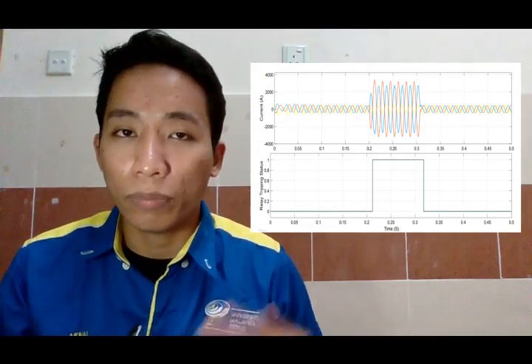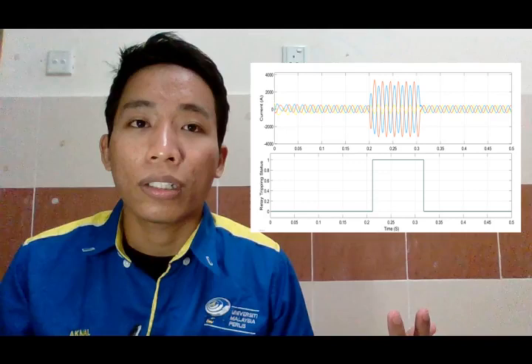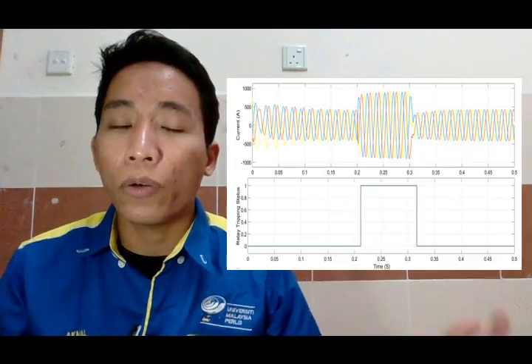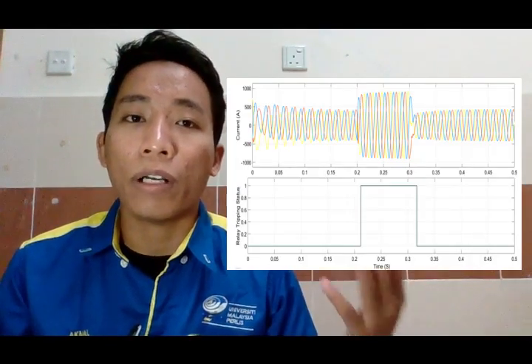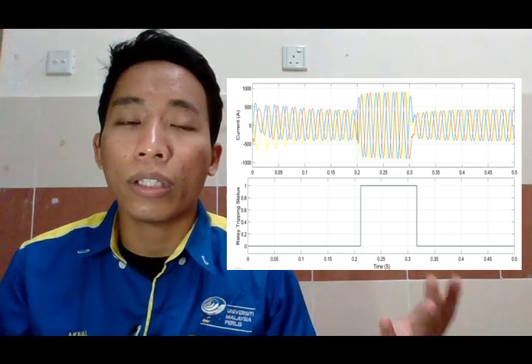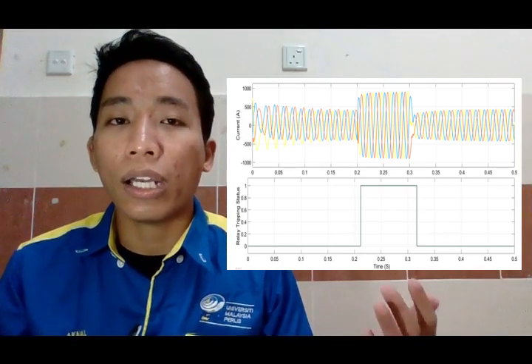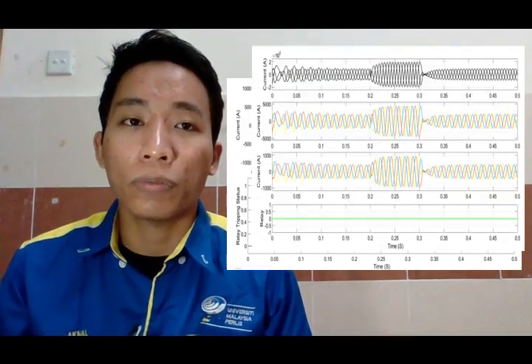The figure presented demonstrates that the presence of high fault resistance leads to a considerable reduction in fault currents. In contrast, for the fault where no resistance is present, and in both scenarios where the fault resistance values are 10 ohms and 70 ohms, the relay effectively detects the fault and generates a trip signal to isolate the faulty section through the circuit breaker. Figures 1 and 2 show the wind farm behavior and performance of the relay during 10 ohm and 70 ohm line to ground faults at the power transformer.